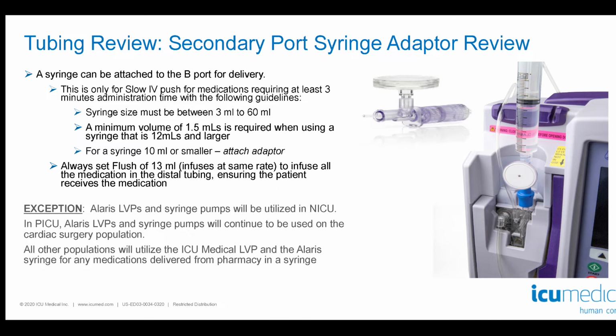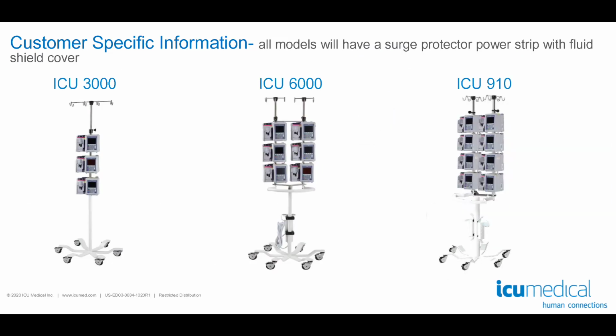An exception to using the B port for syringe delivery is that our Alaris large volume pumps and syringe pumps will continue to be utilized in our NICU. In PICU, Alaris large volume pumps and syringe pumps will continue to be used on the cardiac surgery population, and all other populations will utilize the ICU Medical large volume pump and the Alaris syringe pump for any medications that are delivered from pharmacy in a syringe. We are also getting new IV poles and retrofitting existing IV poles with power strips. Please only plug IV pumps into these power strips and not other equipment such as SCDs.